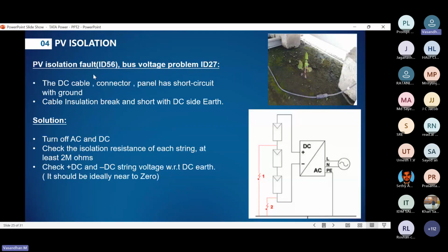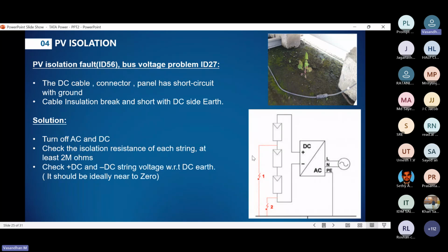Okay. Next, PV isolation. One second, I will check it. Okay, PV isolation, nothing but ID 56 fault will occur. Bus voltage problem. Whenever we have an issue with the connector or a short circuit with the ground, with the string, any panel strings or whatever cable issues, cables break down, or it will short with the DC side earthing also, it will show PV isolation.